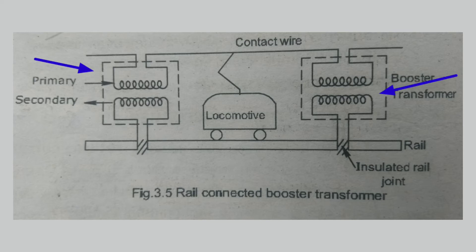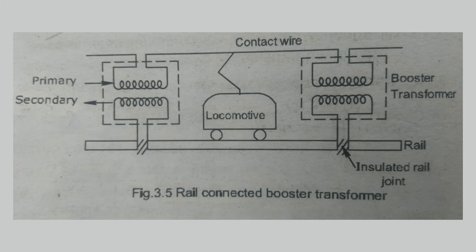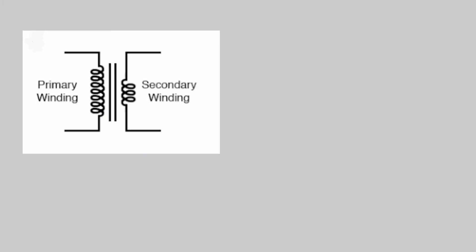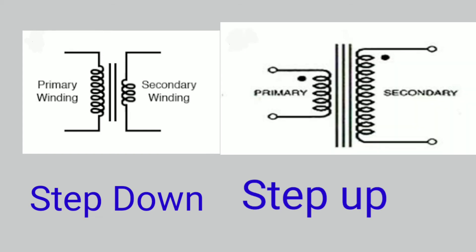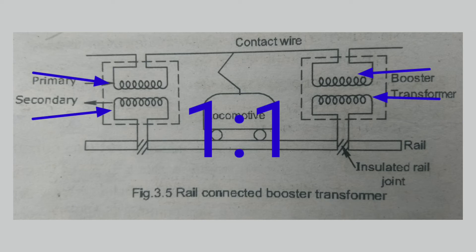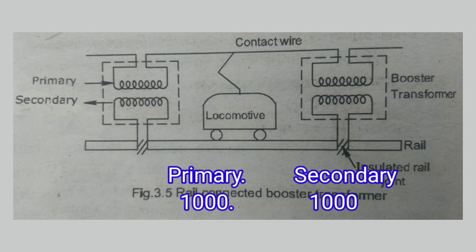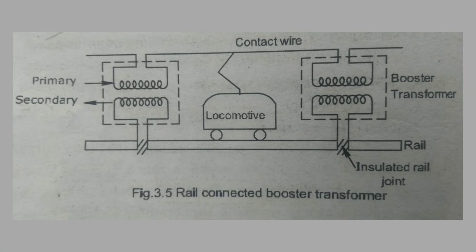To reduce this interference effect on the communication line, we use a Booster Transformer. In the transformer, we use a primary winding and a secondary winding with the same turns ratio. As used in an electric train system, the Booster Transformer has a one-to-one turns ratio — the transformer is one to one.